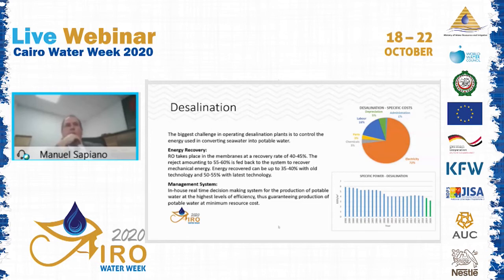of desalinated water. We operate a lot of energy recovery systems, so the brine which is going out of the desalination plant is a source of energy, which is recovered and put back in the system, therefore requiring less input energy. And we also operate management systems on the plants to always operate those membrane lines which are the most energy efficient, and therefore once more trying to reduce the consumption of energy in these plants.